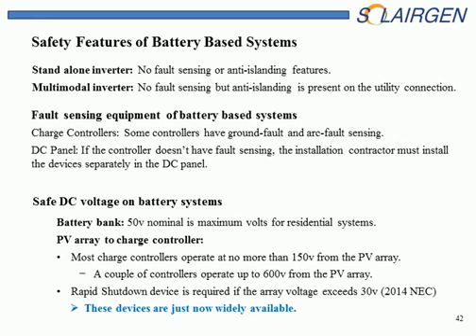If the PV array is on the ground, not a problem. There's going to be a DC disconnect either at the PV array or on the structure. So you can disconnect that and shut down the DC from coming in to the PV system. But the battery bank will still be there, and it'll still be operating at that voltage. So hopefully it's contained well enough that you don't have to do anything with it.